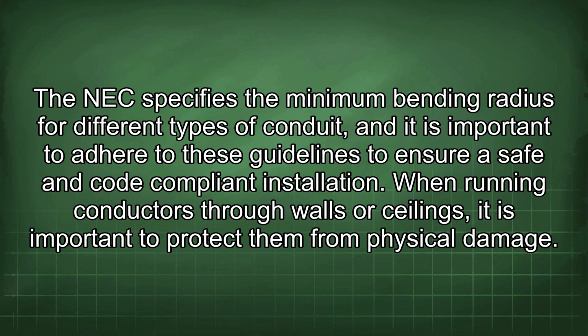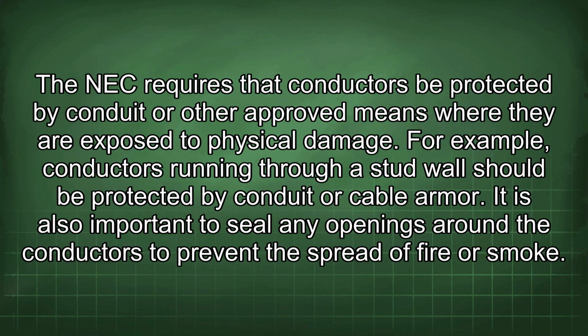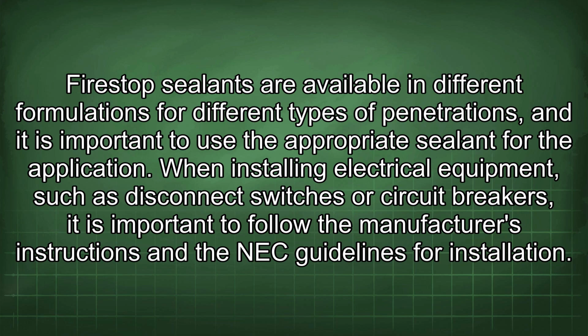When running conductors through walls or ceilings, it is important to protect them from physical damage. The NEC requires that conductors be protected by conduit or other approved means where they are exposed to physical damage. For example, conductors running through a stud wall should be protected by conduit or cable armor. It is also important to seal any openings around the conductors to prevent the spread of fire or smoke.